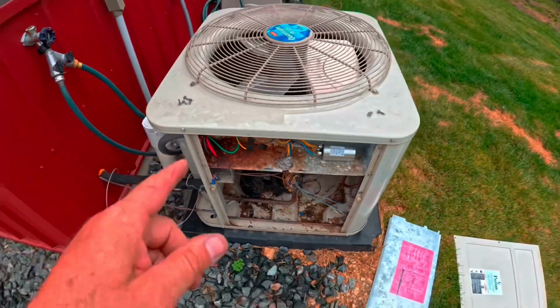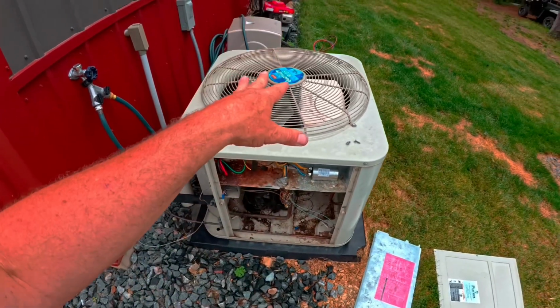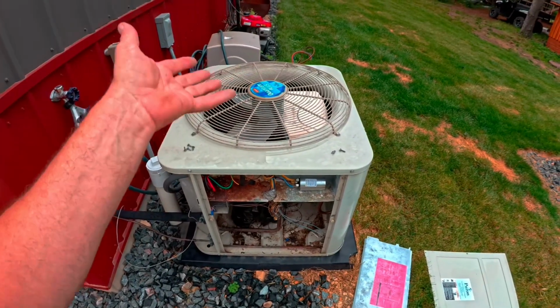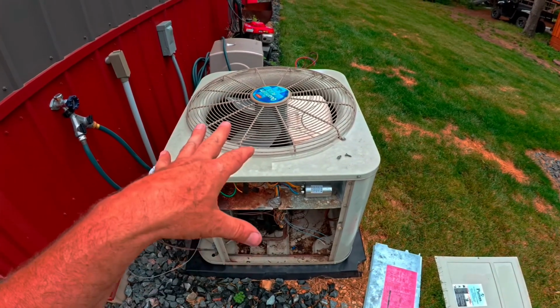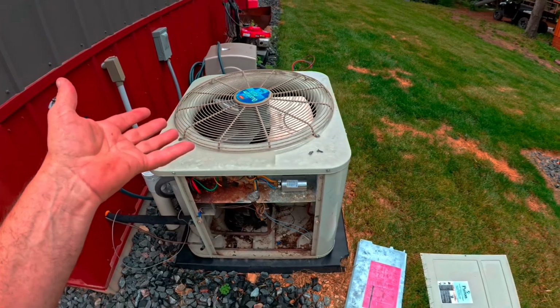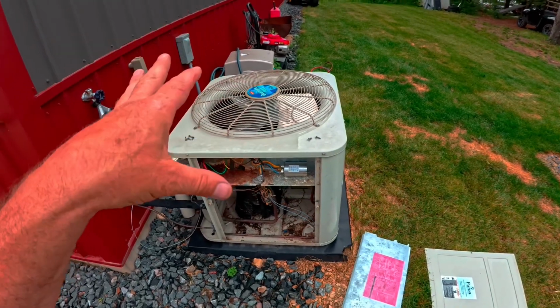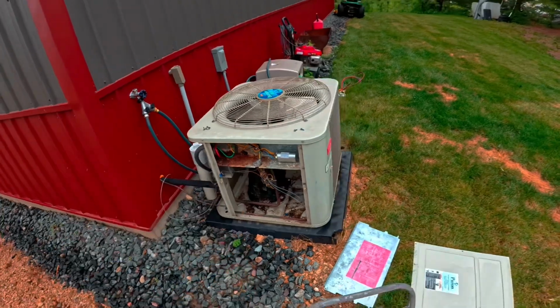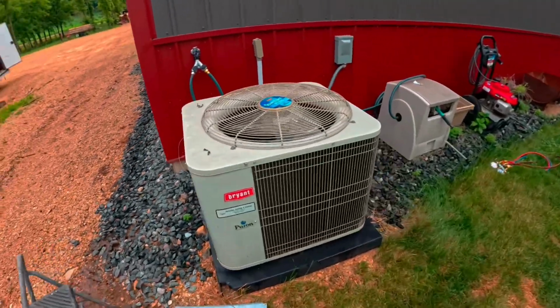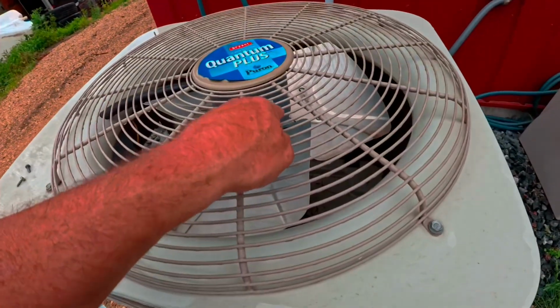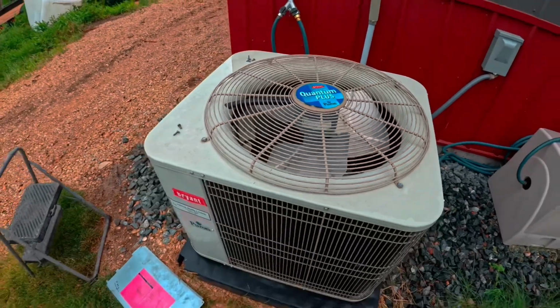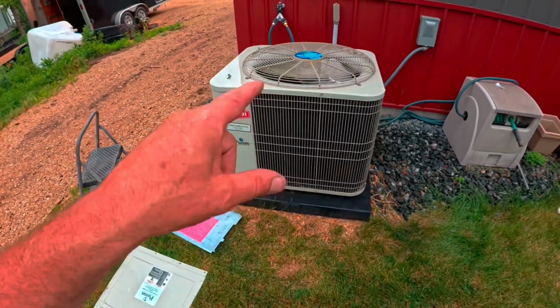If it doesn't take care of it, if you replace that and the fan still won't start, well, then you probably need a new fan motor. Again, it can be replaced. You can do it. You just need to find the exact same fan. The easiest way to do that, everything has a part number on it. Just got to find it and then do it. Again, make sure your power is turned off.